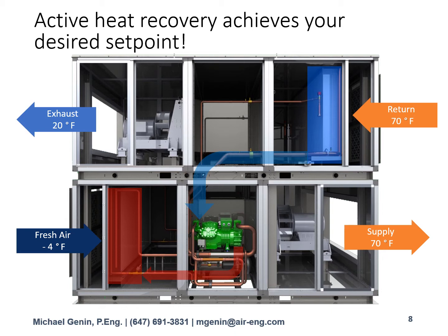This is critical because we don't need top-up energy that's derived from electric or other fossil fuel sources, which can help us achieve our energy savings and greenhouse gas emission reductions. Also, the seasonal efficiency of this system is about 7. So when we compare back to our air source heat pump with the seasonal efficiency of 4, we now have a system that's nearly twice as efficient on the ventilation side.